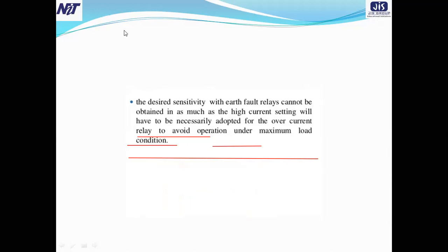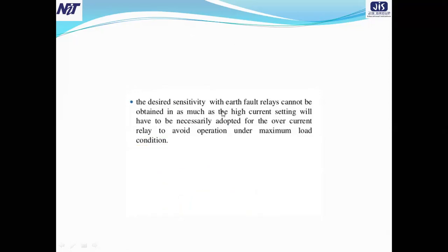Now look at the next part: the desired sensitivity with earth fault relays cannot be obtained, inasmuch as a higher current setting will necessarily have to be adopted for the overcurrent relay to avoid operation under maximum load condition.